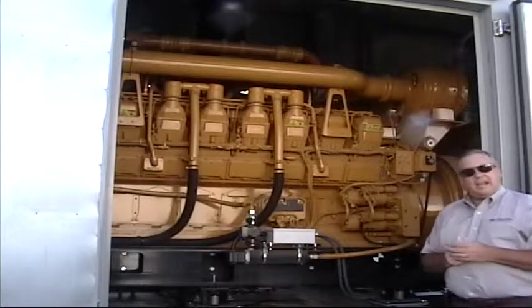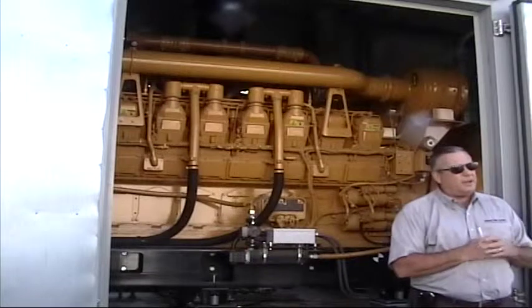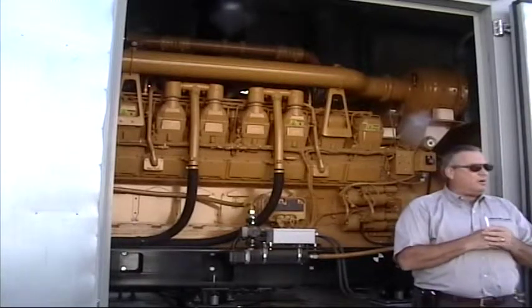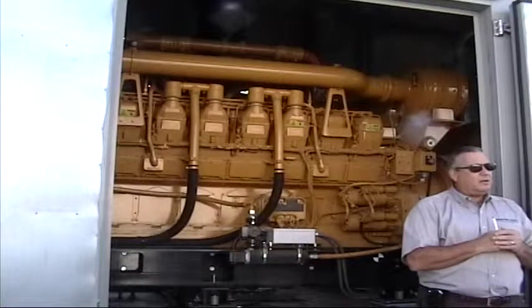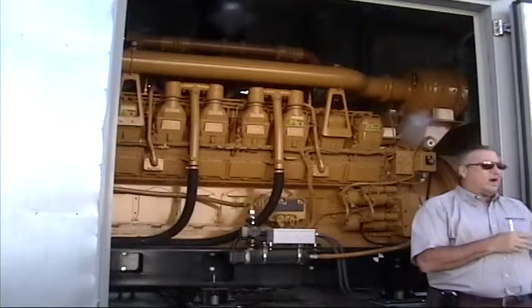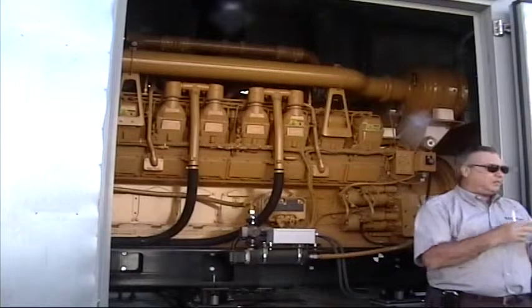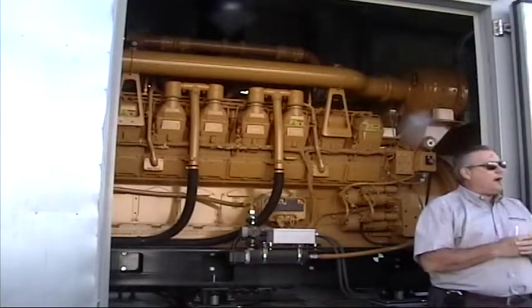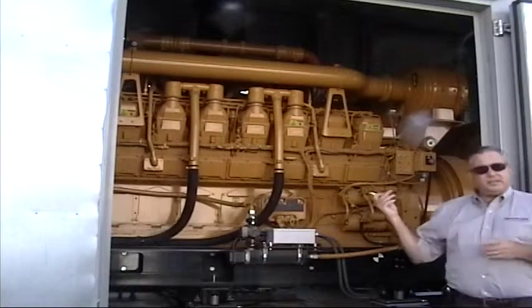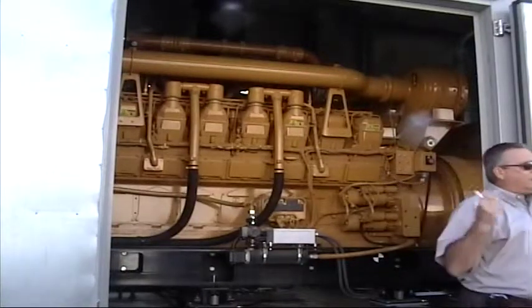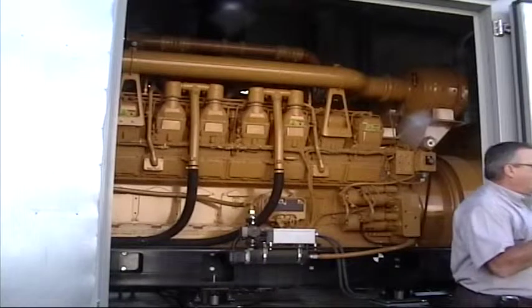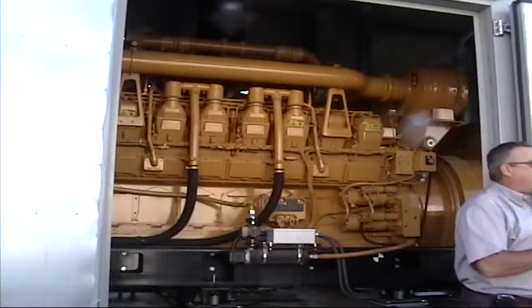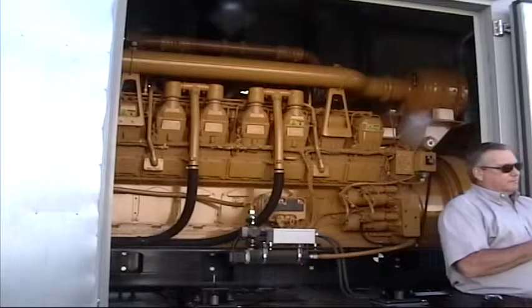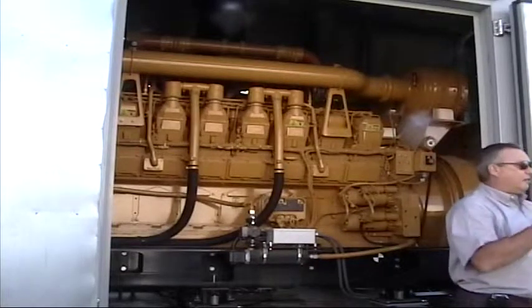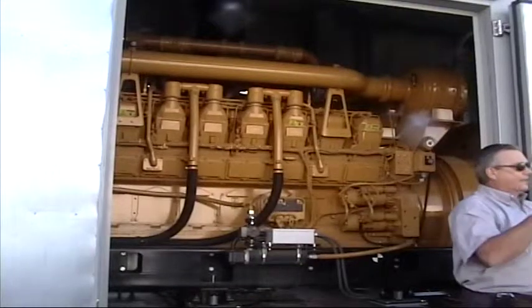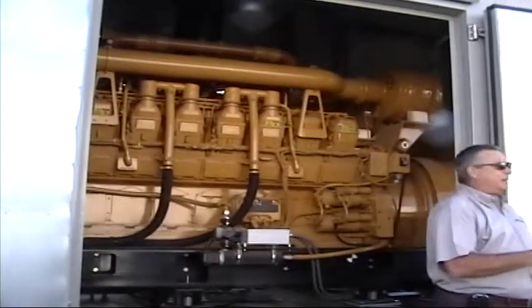And Eddie, I'm not sure where it was set up, 100 to 120. About 140. Okay, so 140 max on it. Oh, 104. Okay, so the range is probably 100 to 120, somewhere in that range, around 104 nominal. And you guys know on a jacket water heater, the reason we want to heat it, even in this environment, is that we like to have a warm start because the engine's called upon to run right away. The block heater keeps that fluid warm around the block. It also keeps the pan warm around the engine, keeps the oil a little warmer than it would normally be, and it helps it to start.